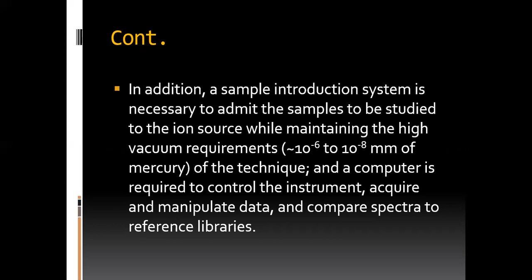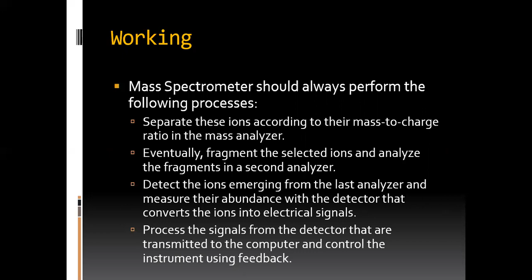Working. A mass spectrometer should always perform the following processes. Separate these ions according to their mass to charge ratio in the mass analyzer. Eventually fragment the selected ion and analyze the fragments in a second analyzer. Detect the ions emerging from the last analyzer and measure their abundance with the detector that converts the ion into electrical signals. Process the signals from the detector, that are transmitted to the computer, and control the instrument using feedback.